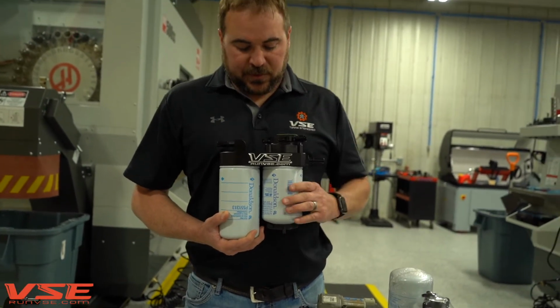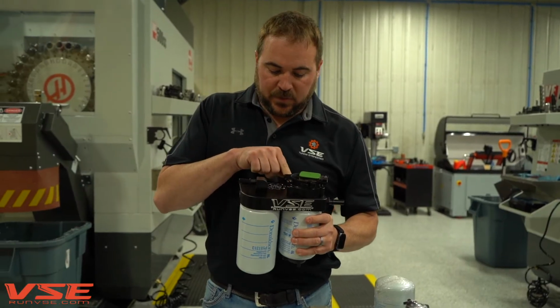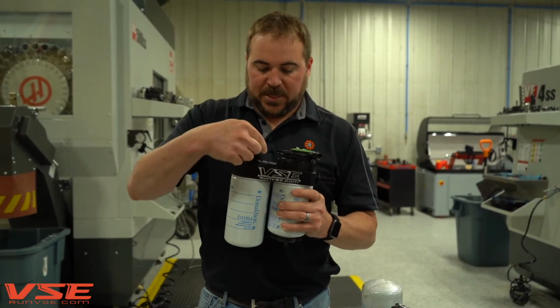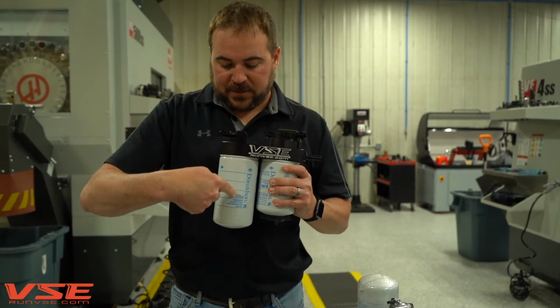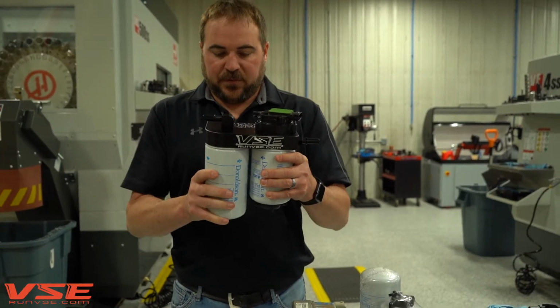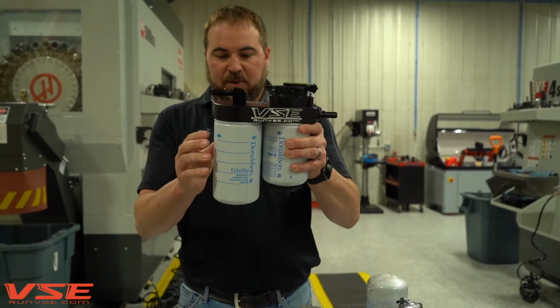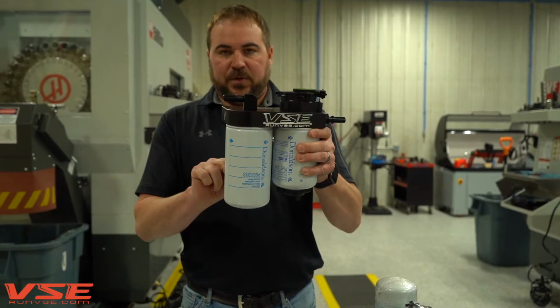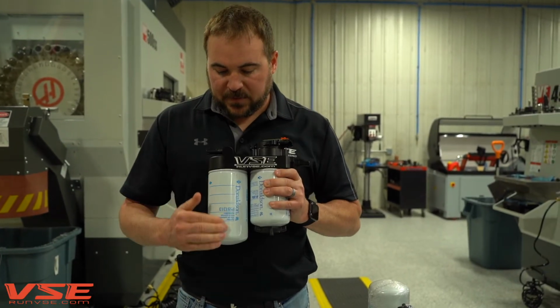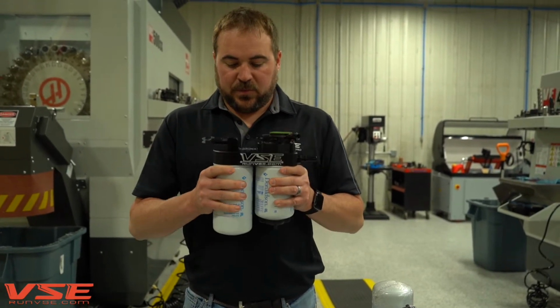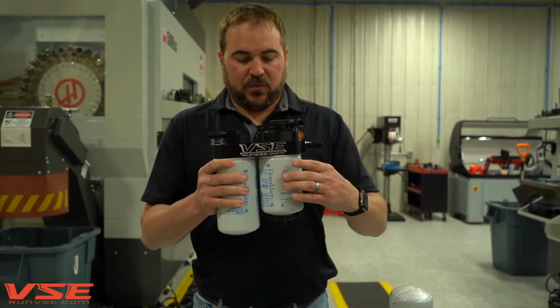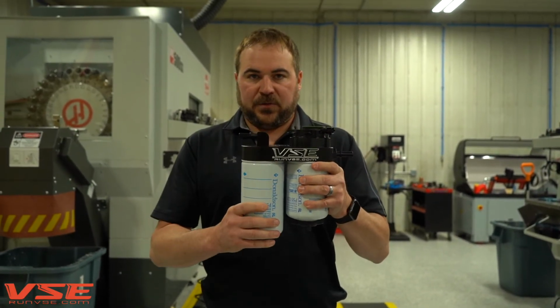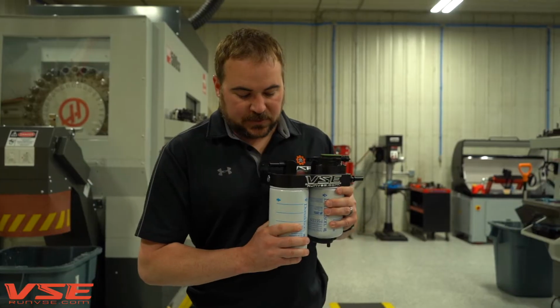And then it's going to send the fuel up through the outlet of this filter, and it's going to discharge it into the inlet of this filter. And this filter is going to filter down to 3 microns. And this part number is P551313. And this is going to be our post filter. So now we have 2 filters to filter out water and fuel, and then filter out all the debris that we see destroy these fuel systems.